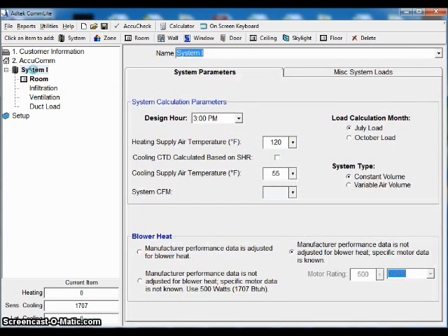On the residential program, we can just start and put in our room or house dimensions. On the commercial program, it's pretty important to tell the program what time of day we're designing for. Are you doing 9 a.m. in the morning? Are you doing 3 p.m., 6 p.m. for a restaurant? With the commercial application, we're not designing on an hourly average. We're designing on what time you want to design. So in this case, I'm just going to choose 3 p.m. I'm doing an office area.